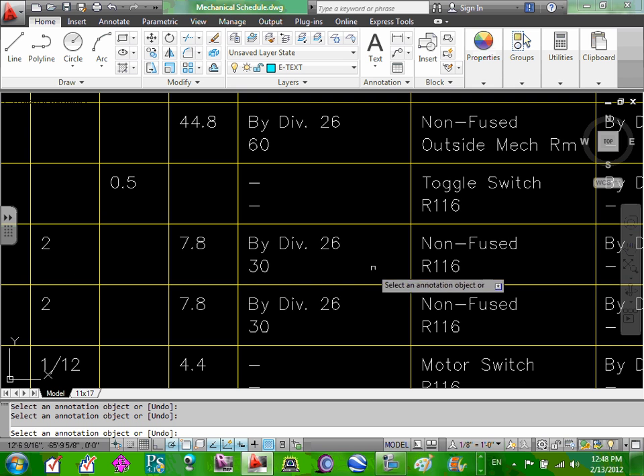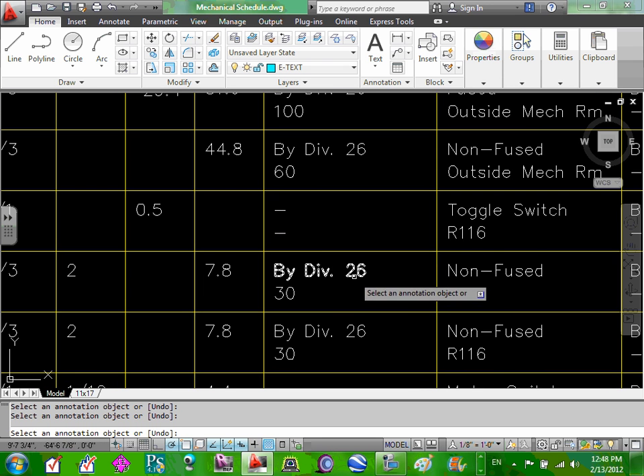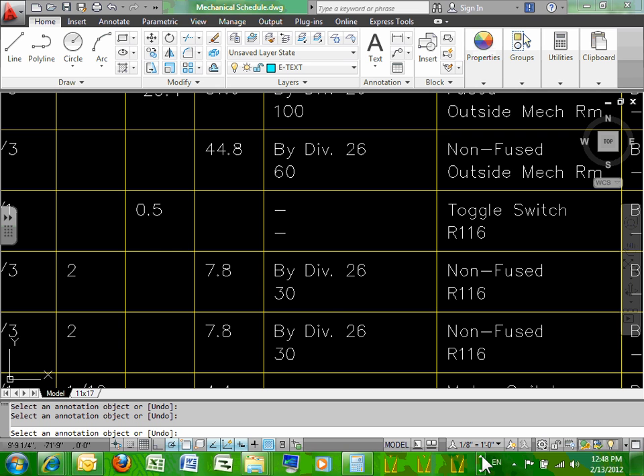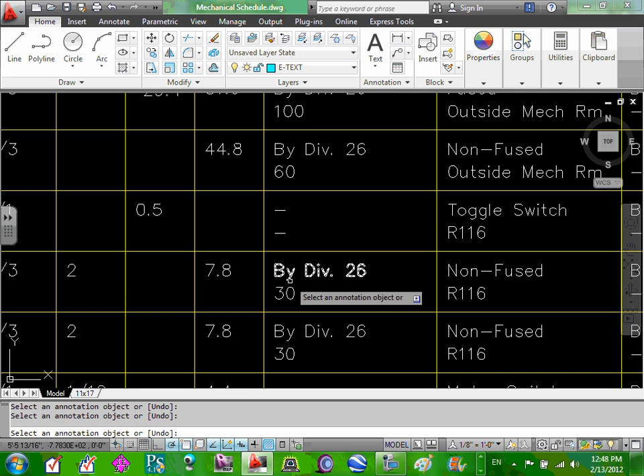So a disconnect type by division 26, disconnect size. I'm not going to do it with my calculator, guys, but you take the full load current, 7.5, multiplied by 1.15, equals 8.625. The next standard disconnect is what? 30. So that's why you come up with the 30 here, right? So perfect, thank you. That's 30.